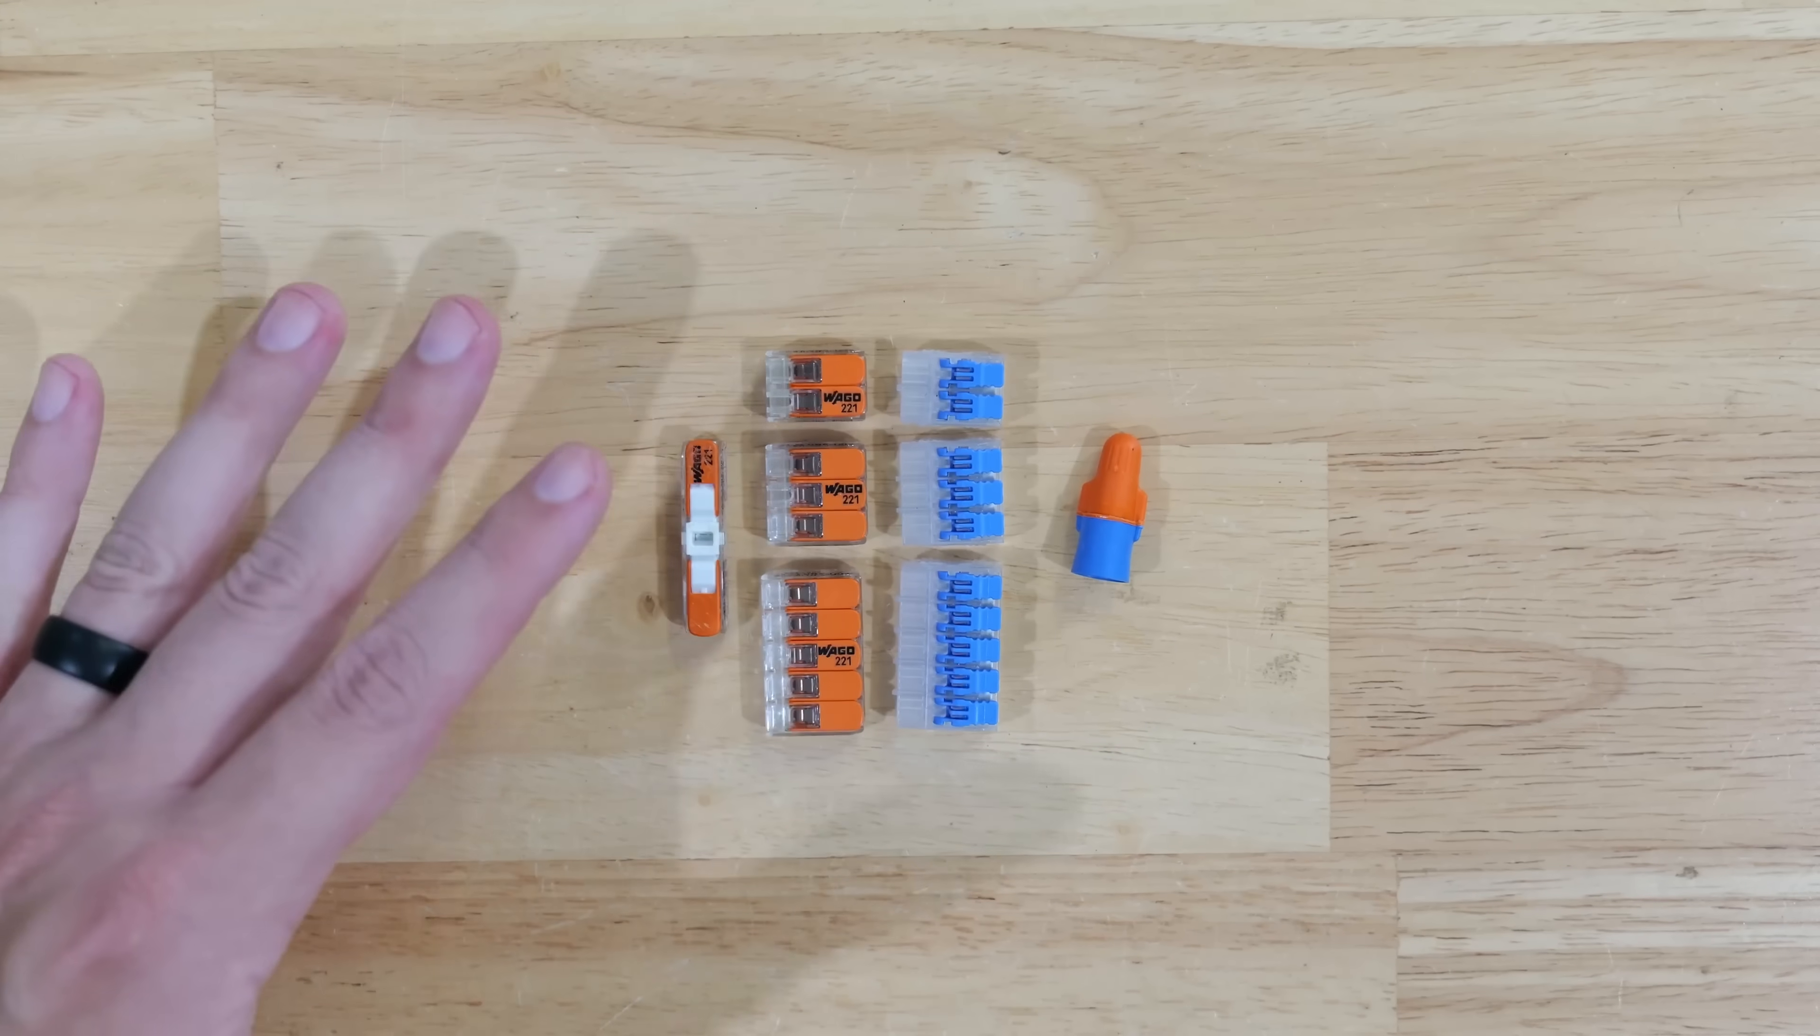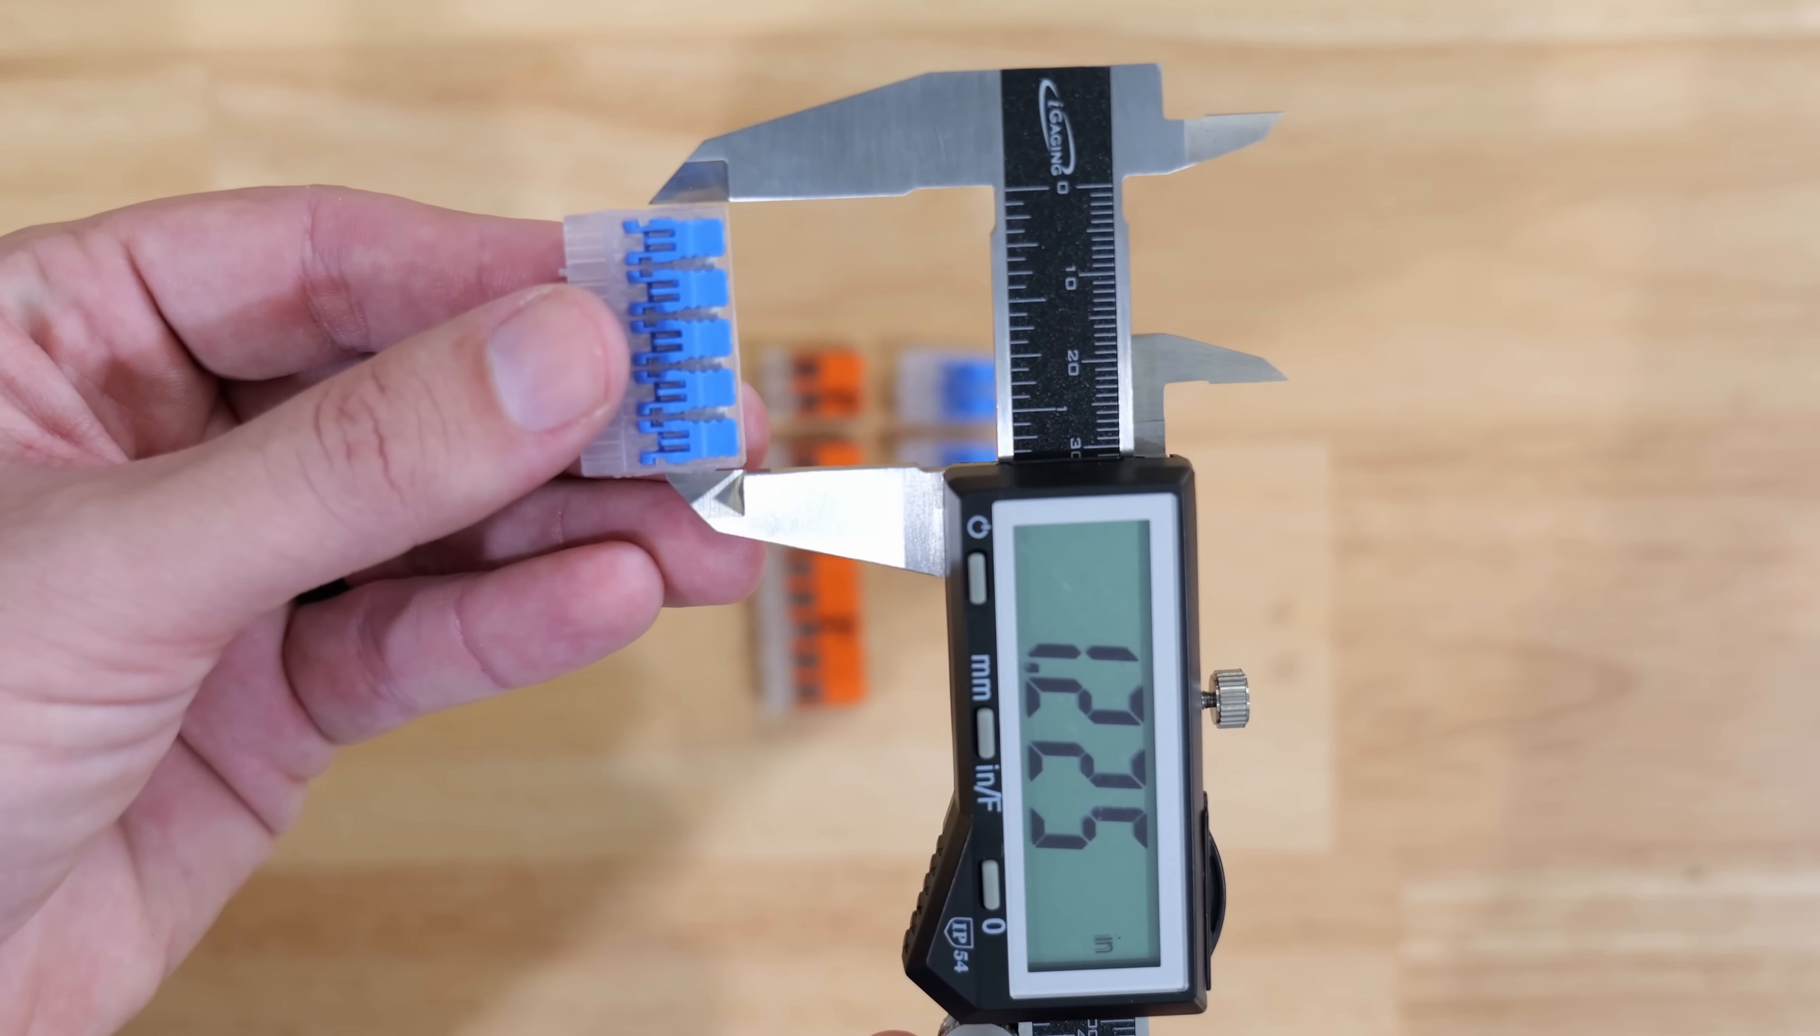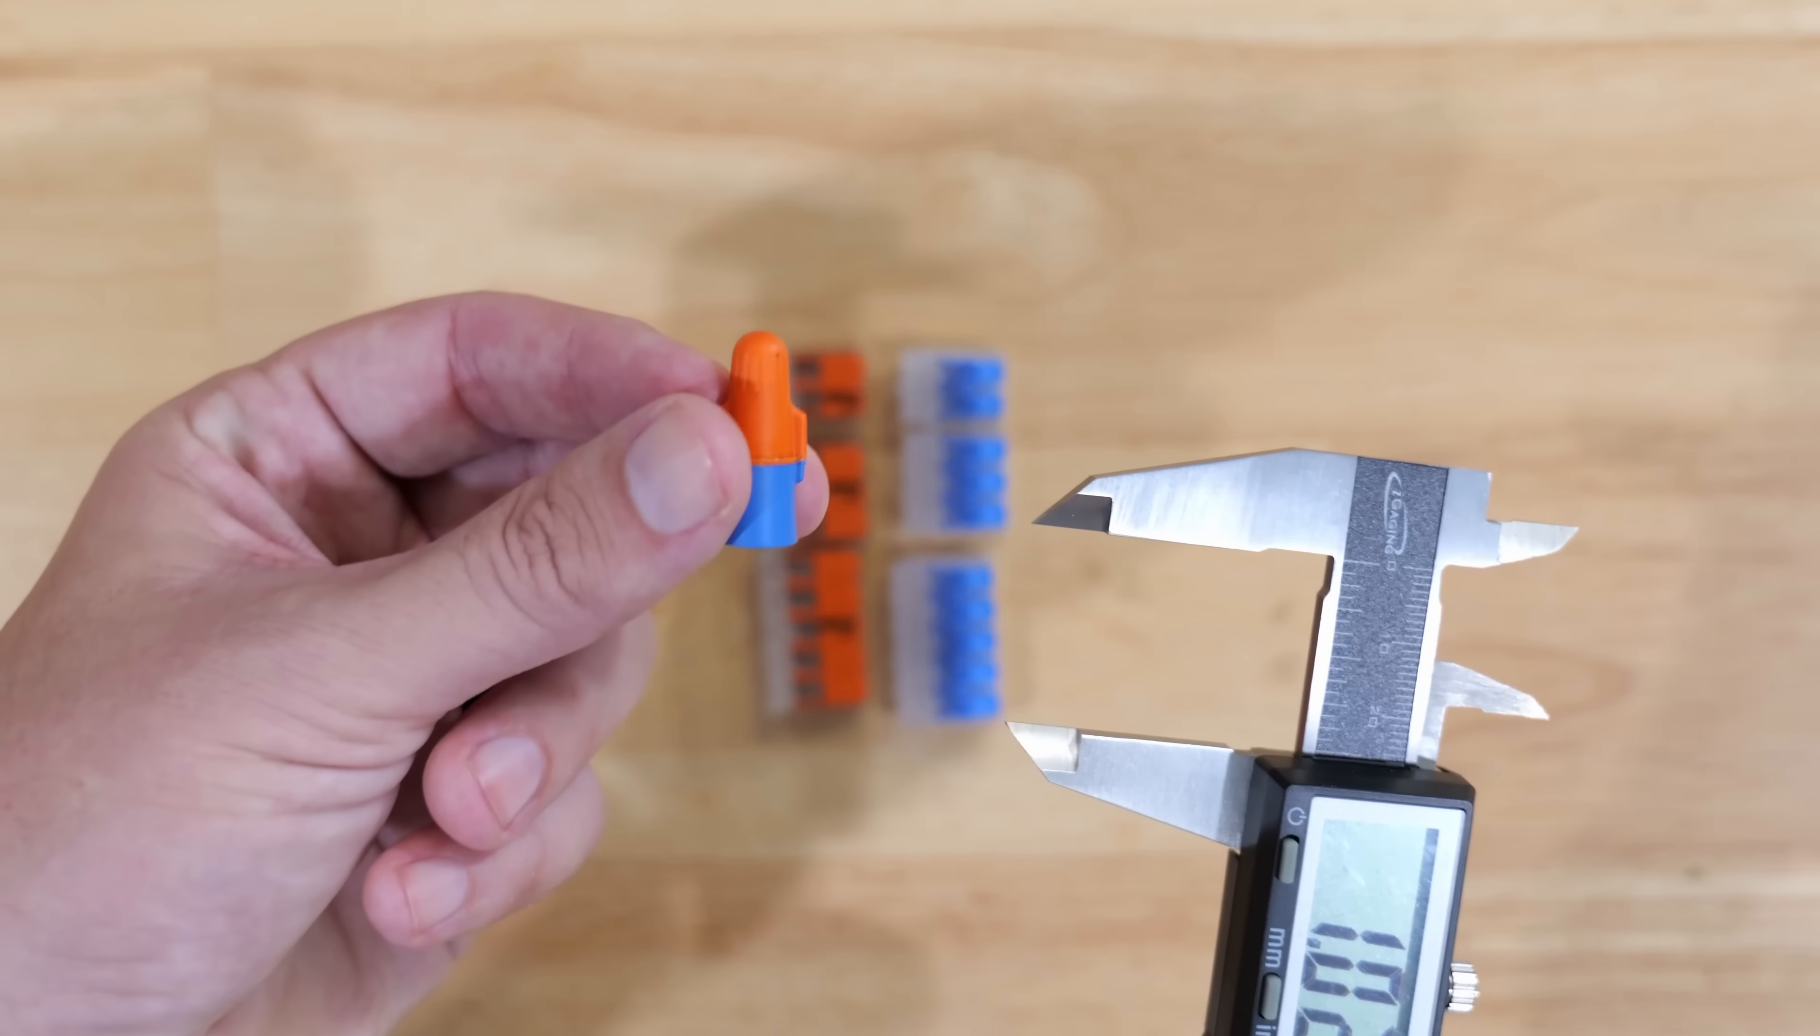One very important factor that a lot of people want to know about when they use different kinds of splicing devices is how much room it's going to take in a box. If we take a look at the 5-port WAGO, we're getting right at 1.17 inches. The Ideal Ensure lever nut is right at 1.225 inches. And the 3M Performance Plus wire nut is right at 1.023.